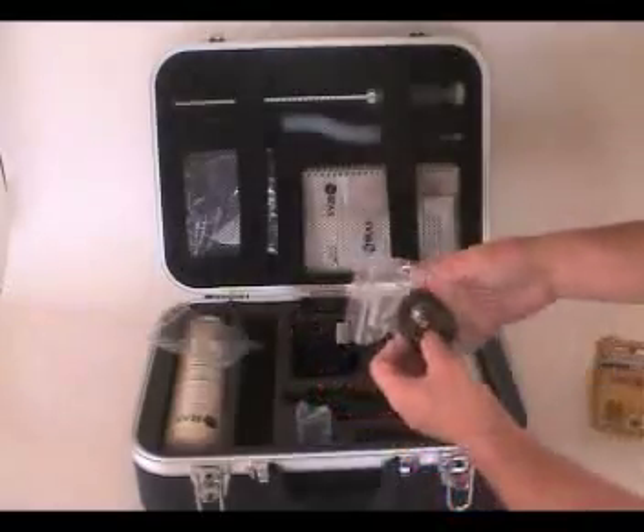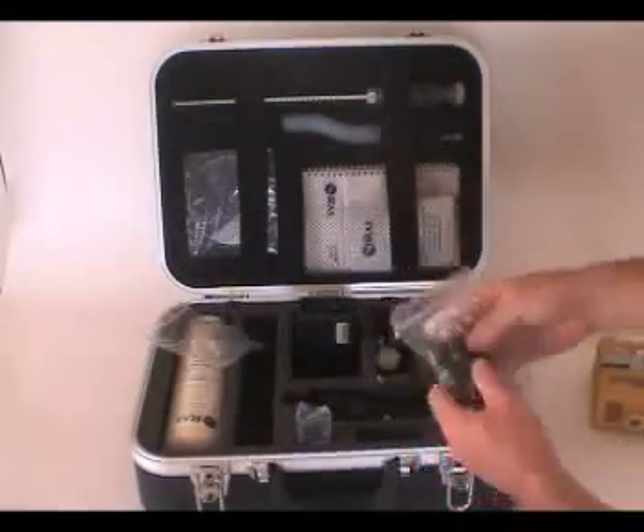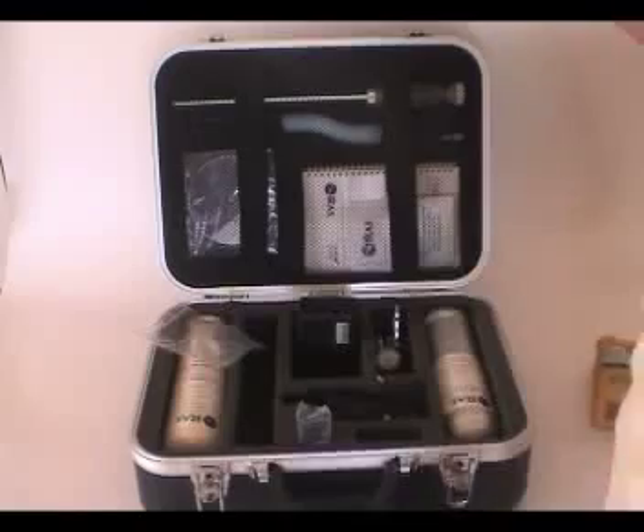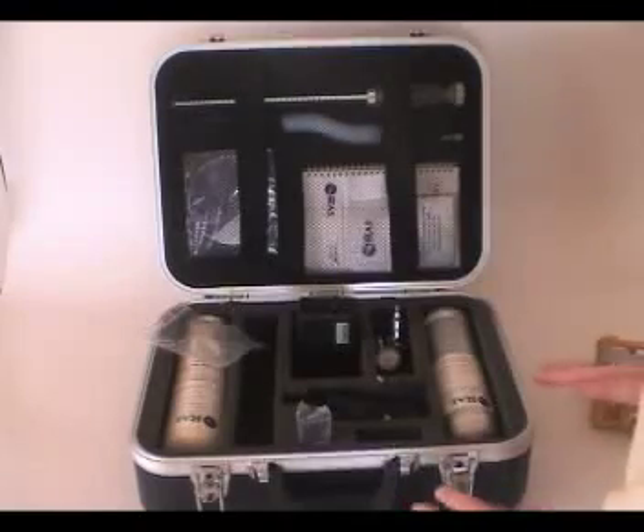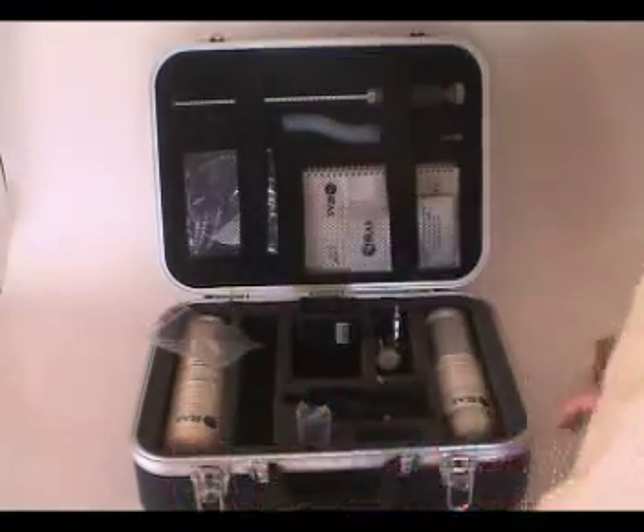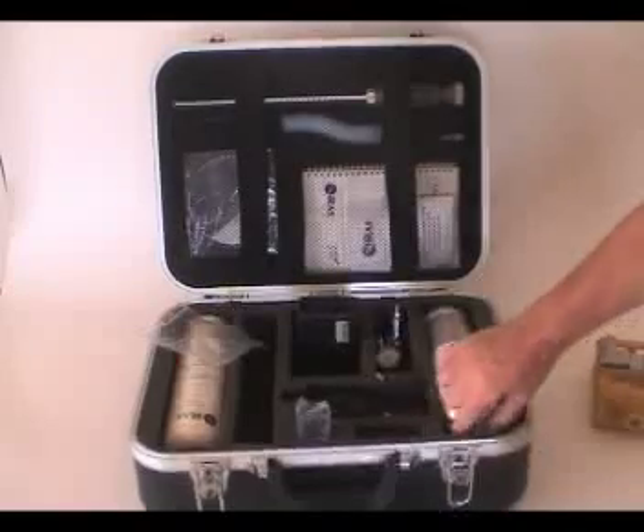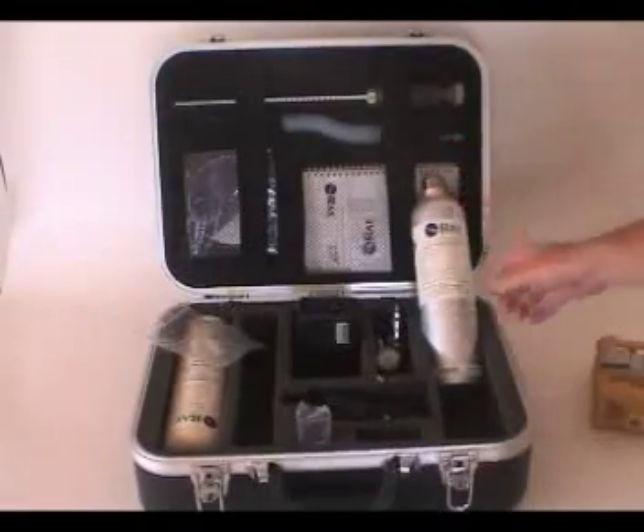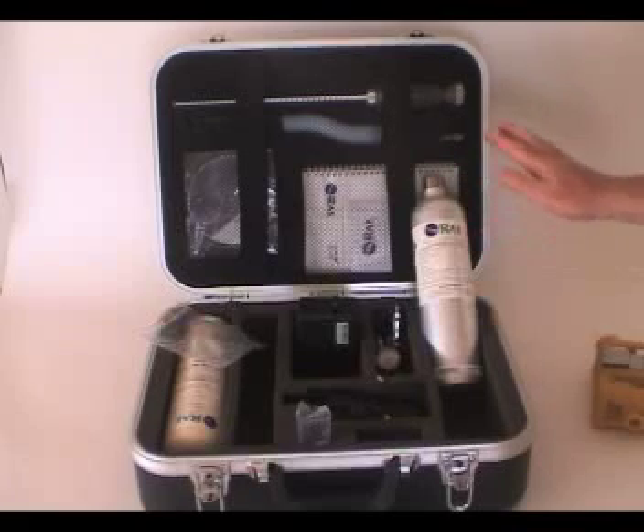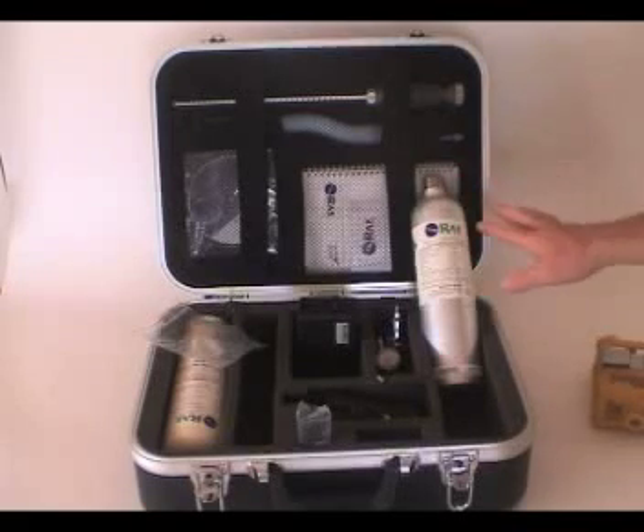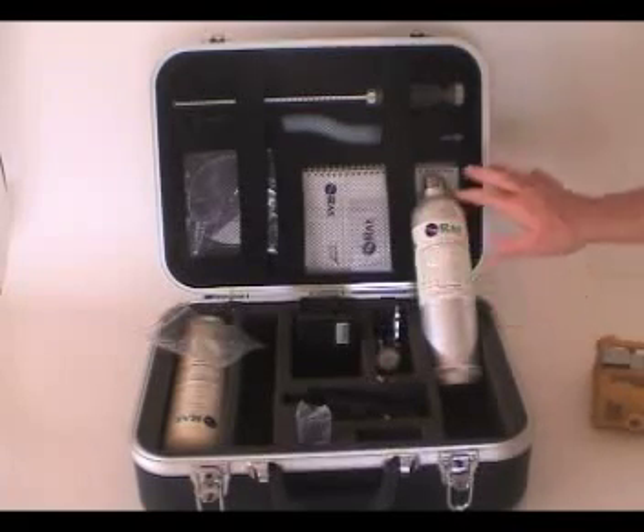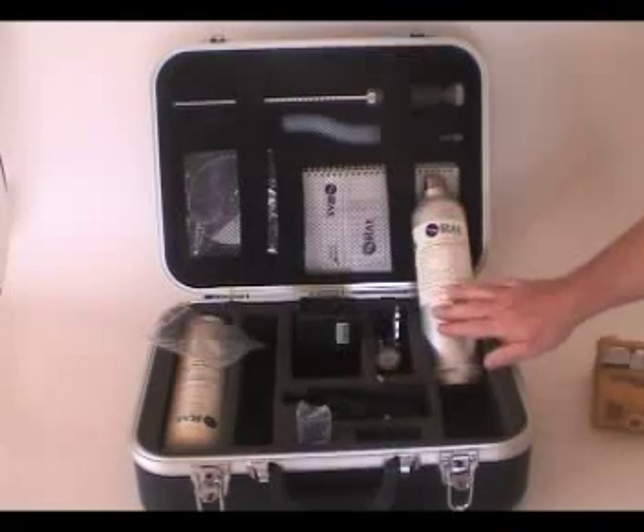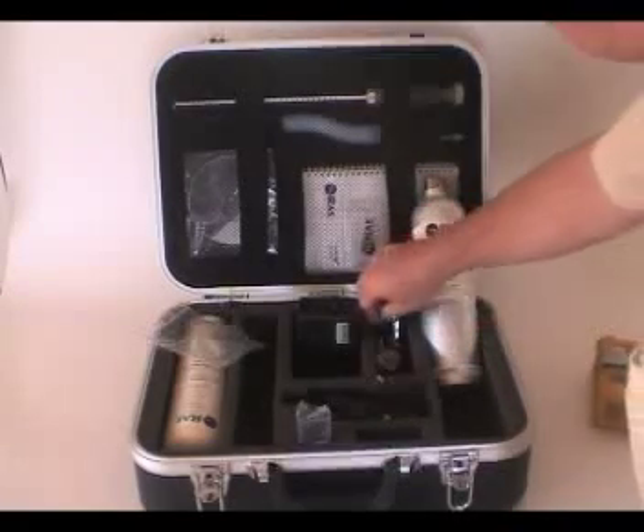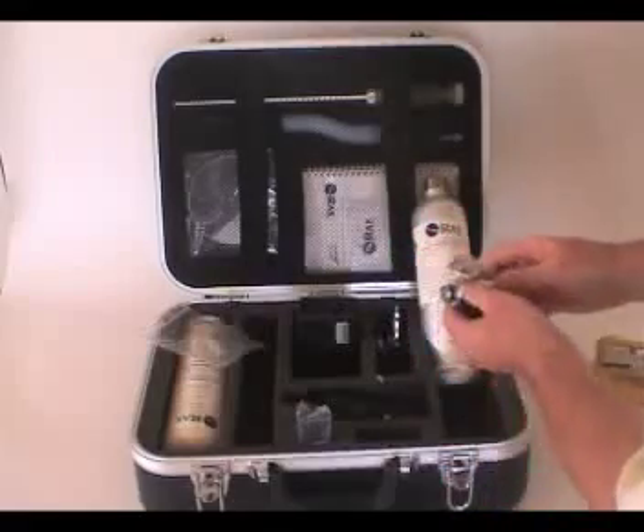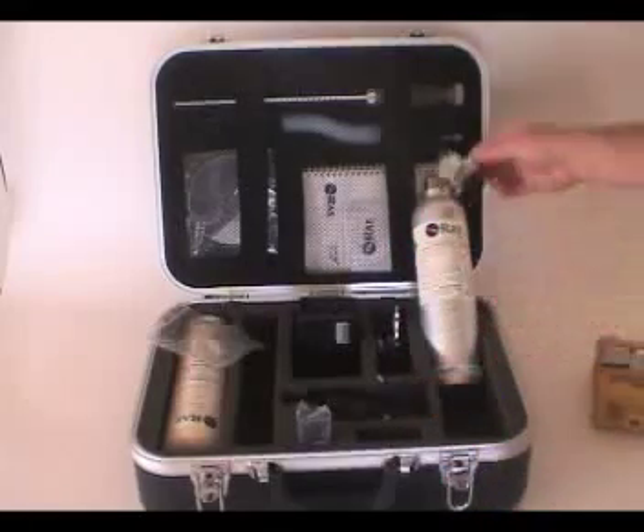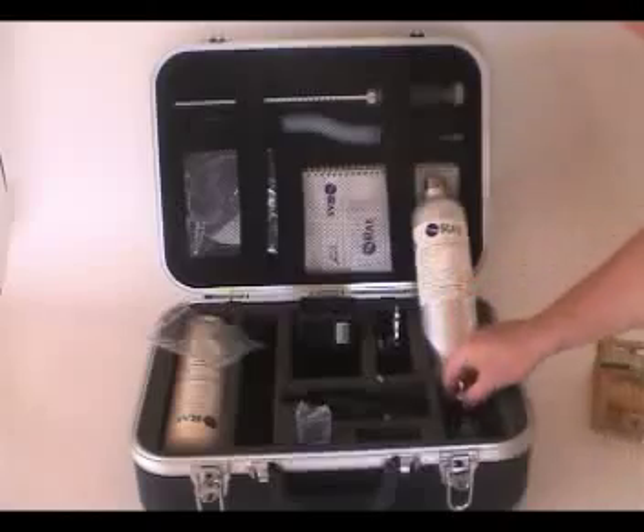This cable is for data logging, allowing you to download data to your computer. For calibrating, we have 2 cylinders of calibration gas. The first is a quad mix with 4 gases: hydrogen sulfide, carbon monoxide, methane, and oxygen, balanced in nitrogen. This is an aluminum 34-liter cylinder using a regulator like this one, with male threads for a female threaded cylinder.